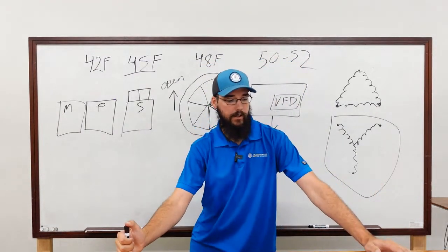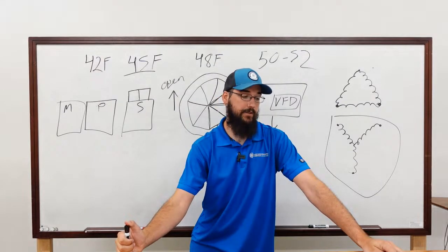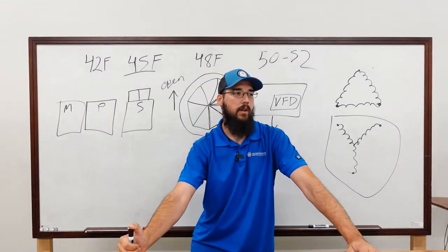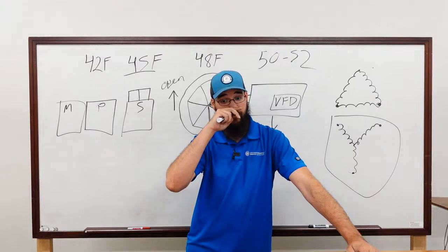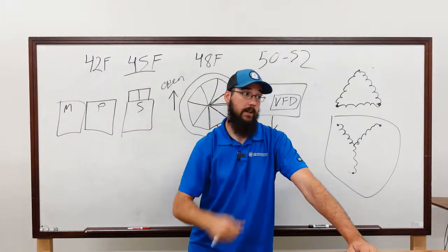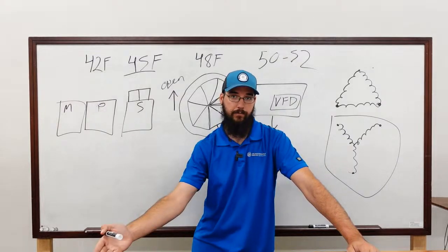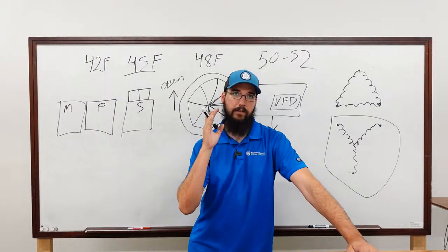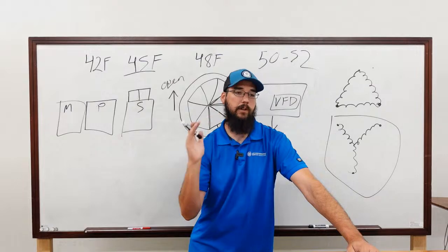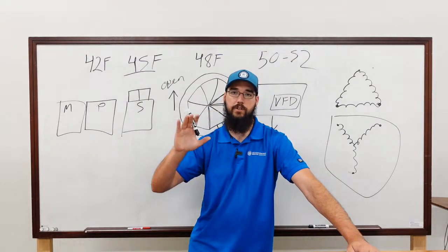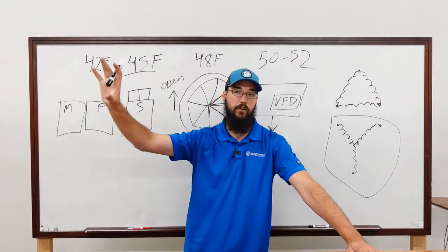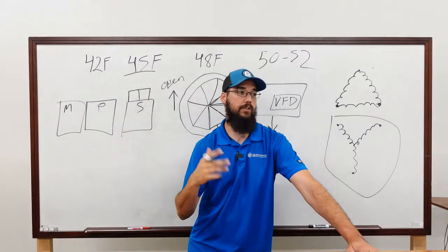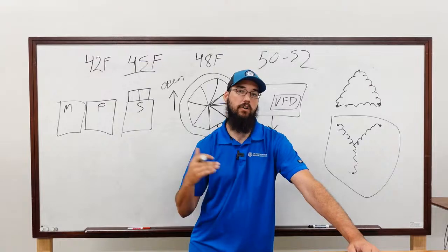Solid state was actually some pretty interesting stuff. It was a precursor to VFD. Imagine, if you're familiar with SCRs, the technology for heaters. You've got a silicon controlled rectifier, which is the solid state, and it essentially did a pulse width modulation signal to do exactly what Sterling just said. It's a soft start, and it's just another alternative to a Y delta. A Y delta is a type of soft starting system. Across the line would be considered a hard starting system.